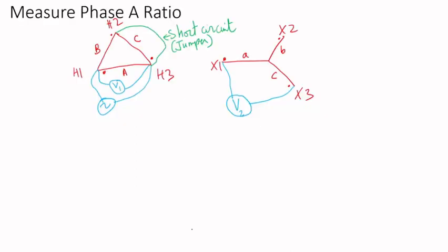In this video, I'll talk about a different method to measure turns ratio when the neutral of a Y is not accessible. In other words, the neutral is not brought out and it's not grounded, so you can't access it, so you can't measure phase to neutral voltage. In a previous video I made, I covered a different method. This is another well-known method which is documented in IEEE, for instance.